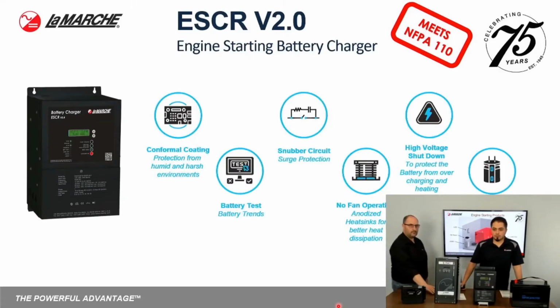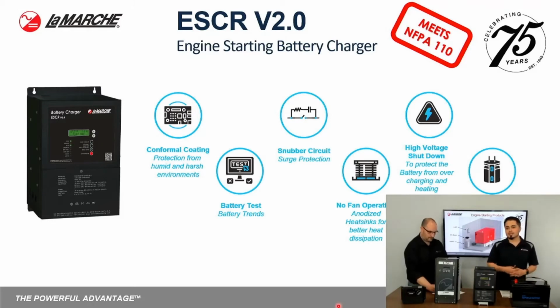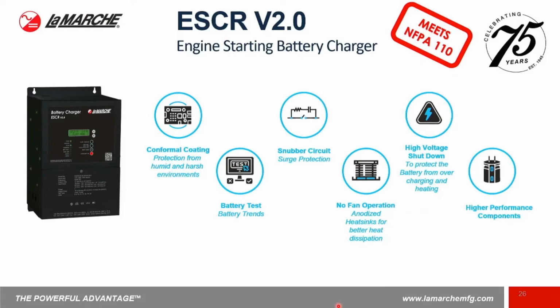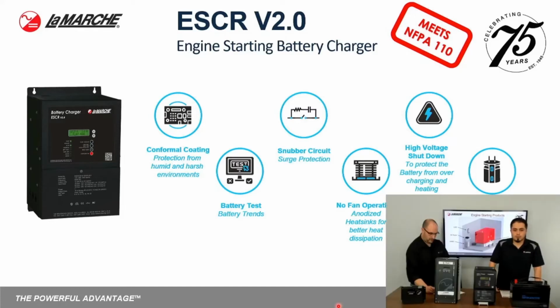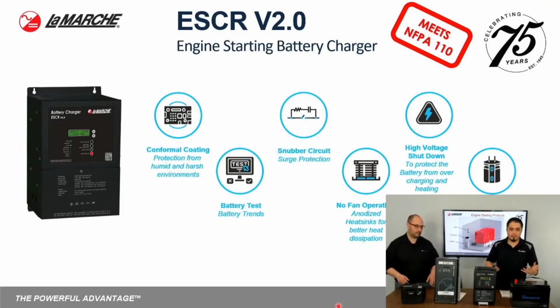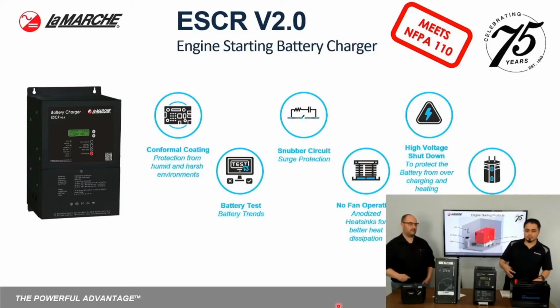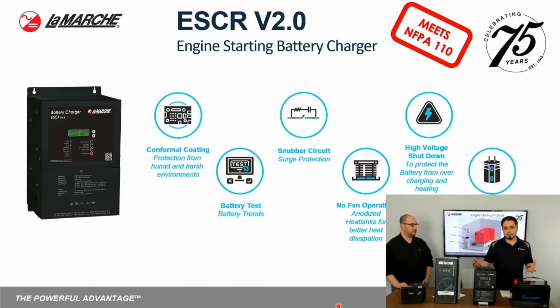Now some of the differences between the ESCR and our ESCR V2. You're going to have updated characteristics in the form of conformal coating. You can see here that we have updated some of the ruggedness of the unit itself with conformal coating, which improves protection from humidity, harsh environments, and salt-laden environments. A battery test feature was added to give you that testing capability when connecting from a battery charger to your battery, or to show if there are any loose connections from one point to another. There is also a snubber circuit to improve reliability and surge protection.